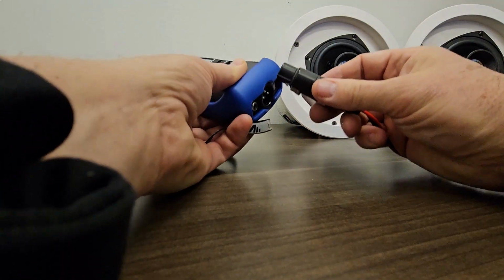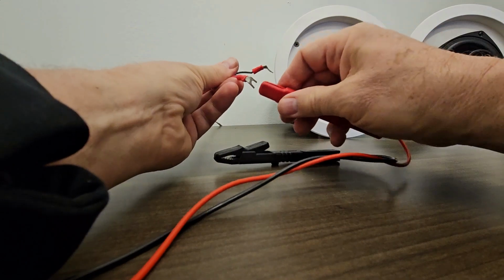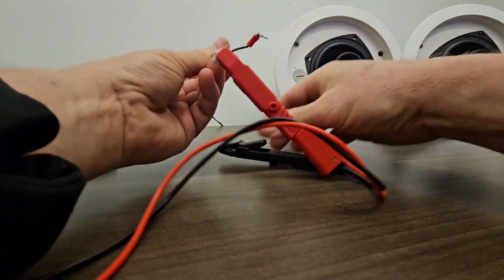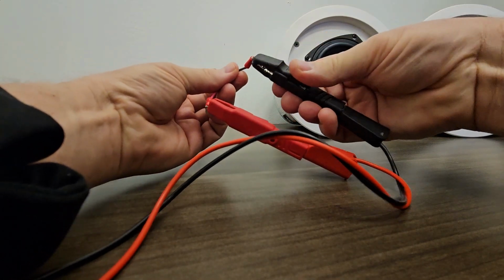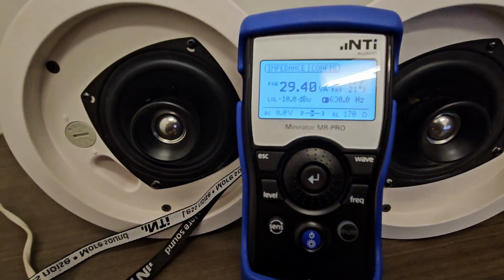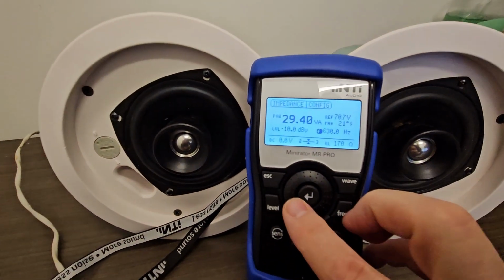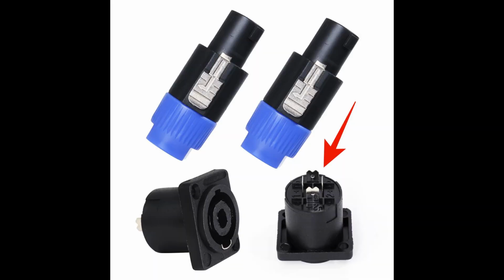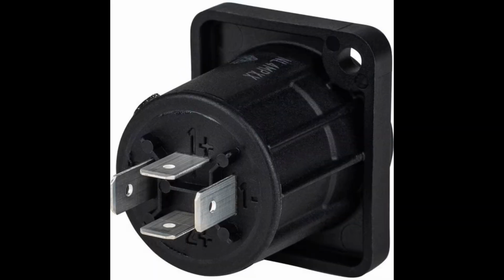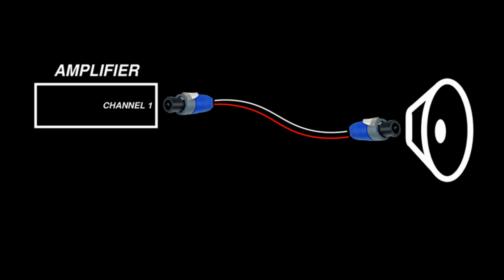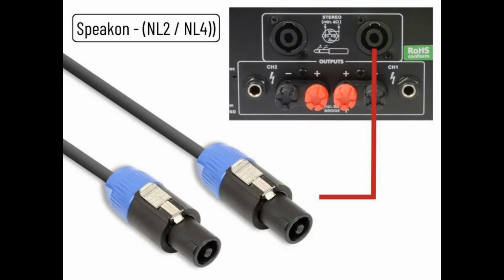Now you are ready to measure the speaker load for each speaker circuit. Simply connect the test leads to the speaker wire, then record the value to your test documentation. Each test measurement kit includes a Neutrik female connector, so you can easily connect to the male Neutrik connector of the speaker circuit. After the impedance measurements have been taken, connect the speaker wires back to the amplifiers.